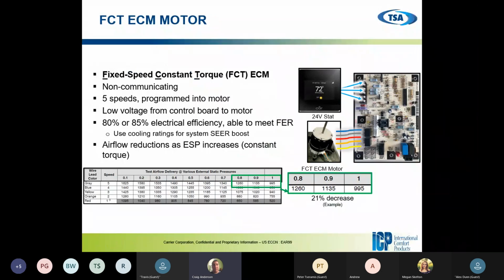Fixed speed, constant torque. This is our X13 motor that we're all pretty familiar with. This is a 5-speed motor, 24 volt terminals going to the board from the motor. Same as standard PSC.